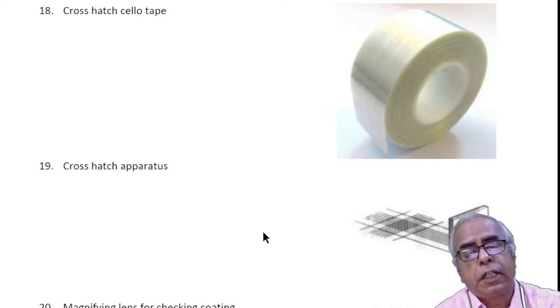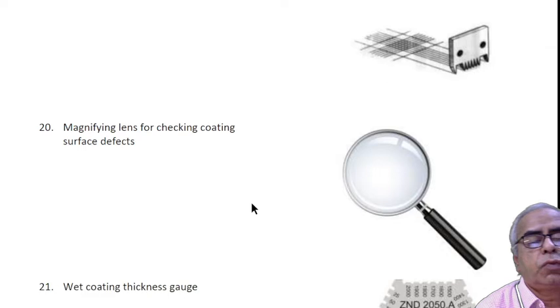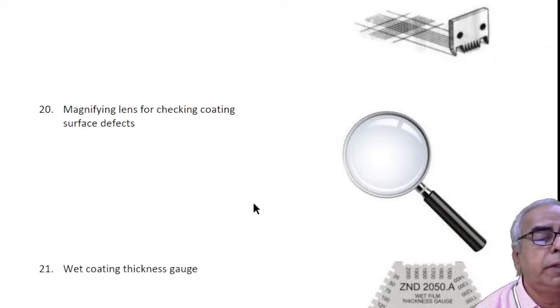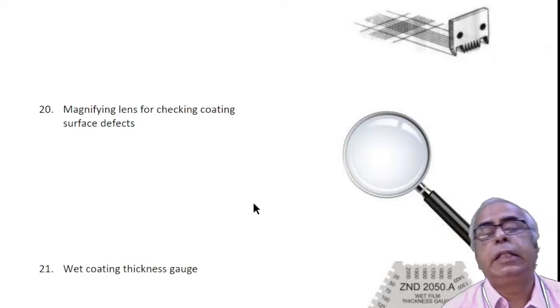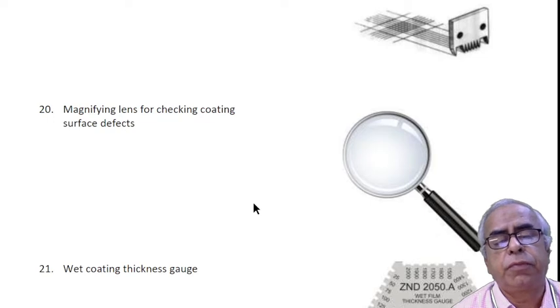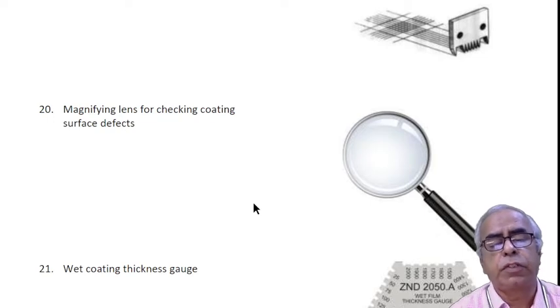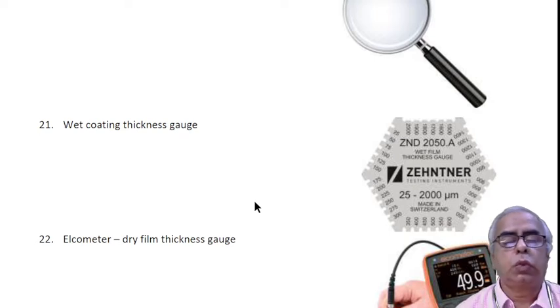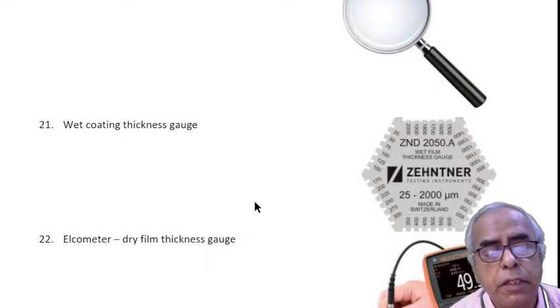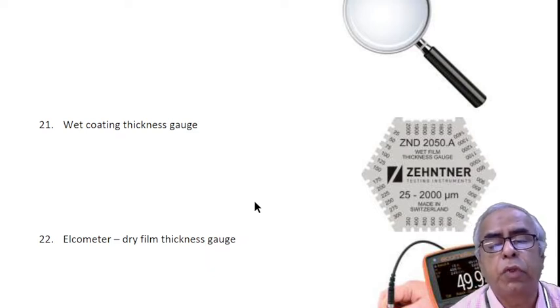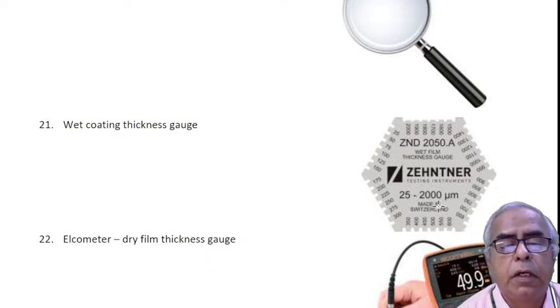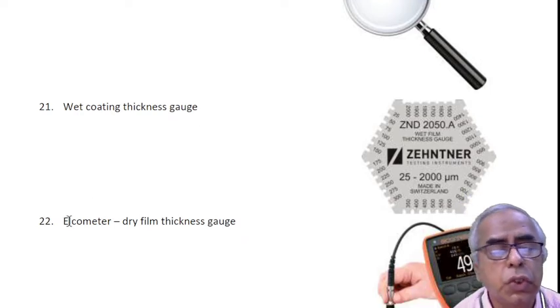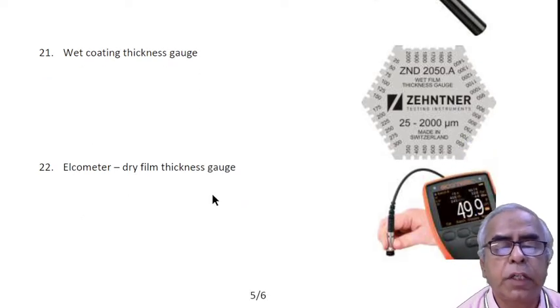Magnifying lens is useful for checking coating surface defects. We have coating thickness gauge for measuring dry film thickness and wet film thickness. These things can be easily studied. For wet coating, this kind of coating thickness gauge is used. For dry film thickness, we can use the Elcometer.